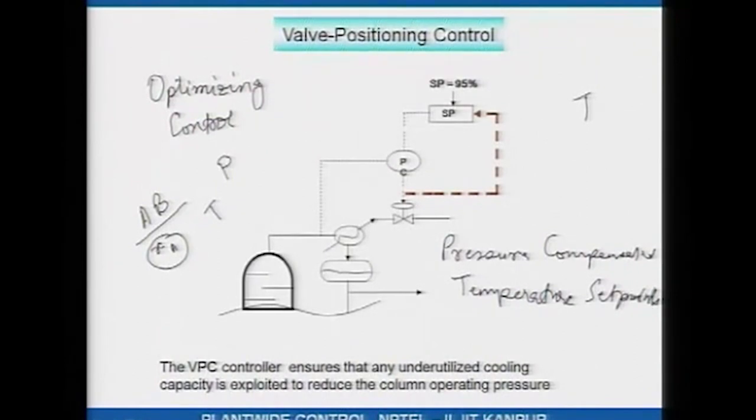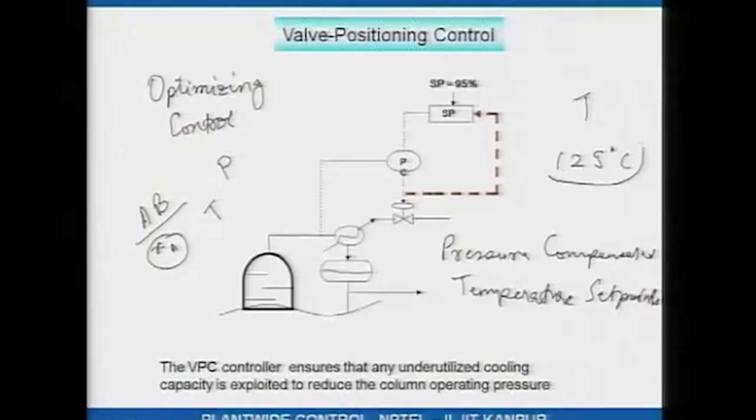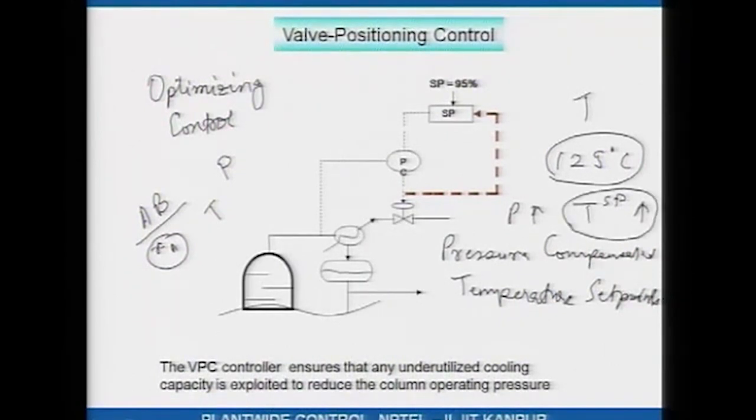To clarify further: if the column is operating at 1 atmosphere and the temperature set point that gives the right separation is 125 degrees Celsius, and the operating pressure of the column goes up because of the action of the valve positioning controller, then for the same separation at the higher pressure the liquid will boil at a higher temperature. So if pressure goes up, the temperature set point should also go up. By how much depends on the mixture being separated. Please be aware that to realize energy savings while implementing temperature control, the temperature set point must be adjusted depending on the current pressure of the column.